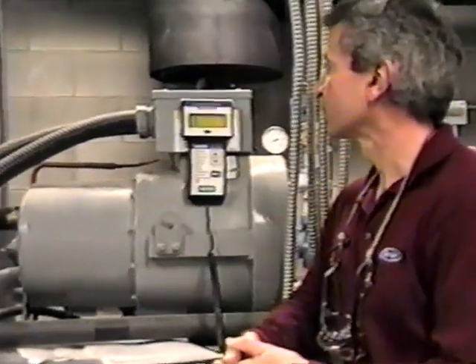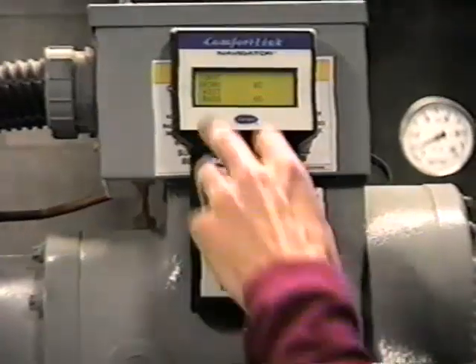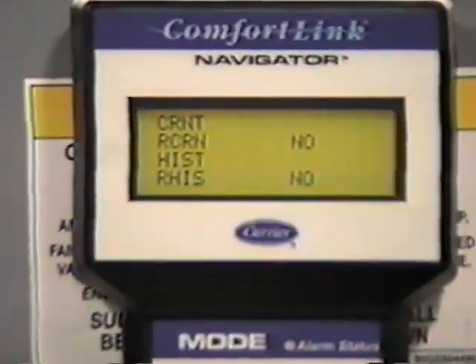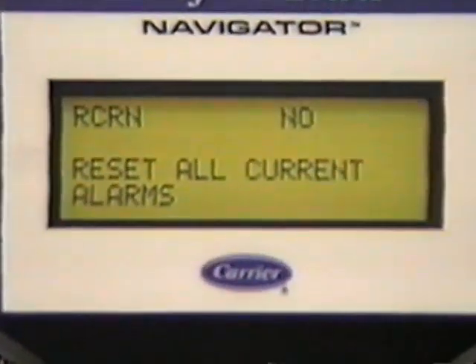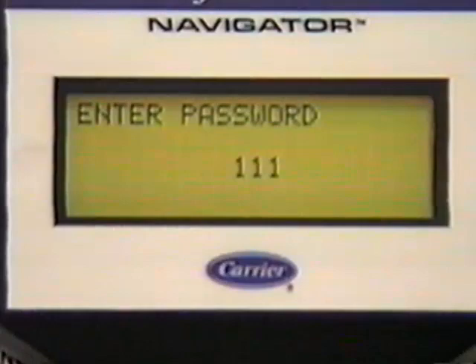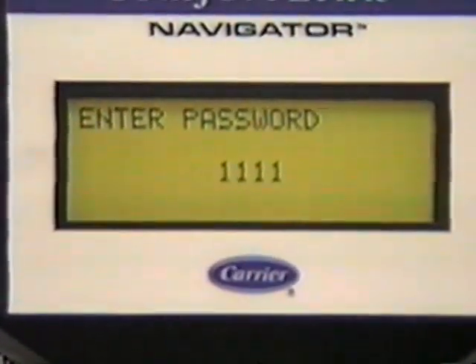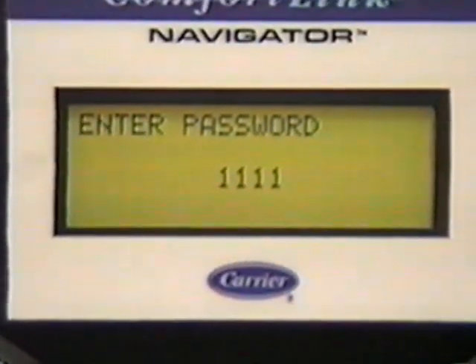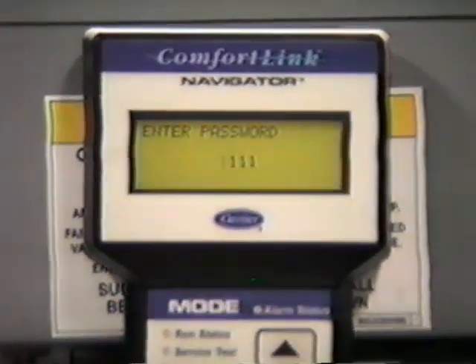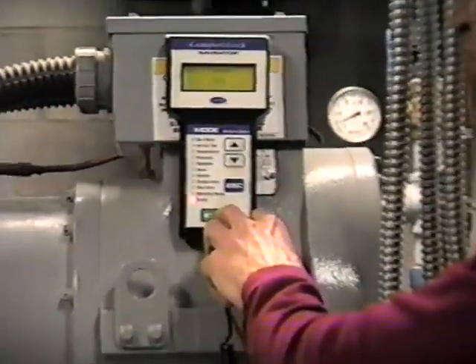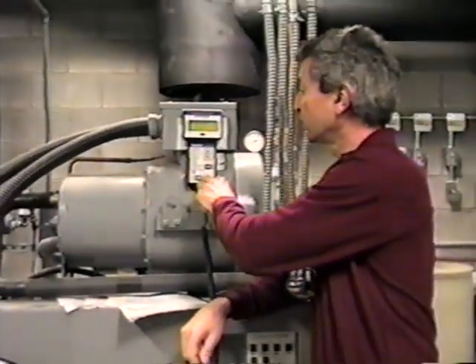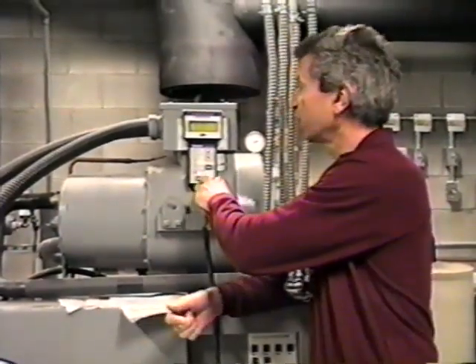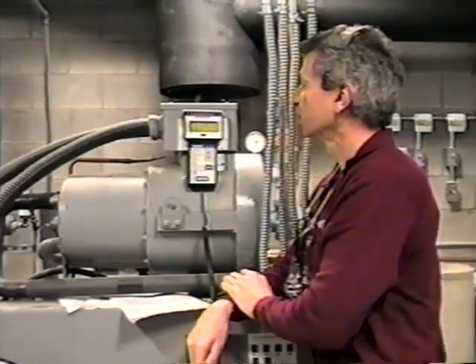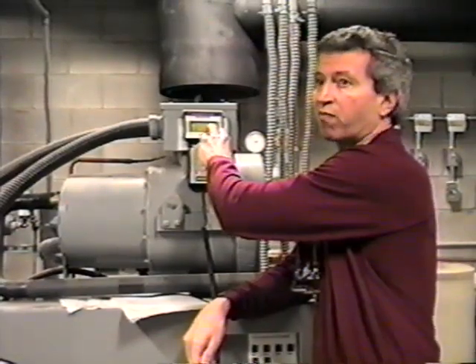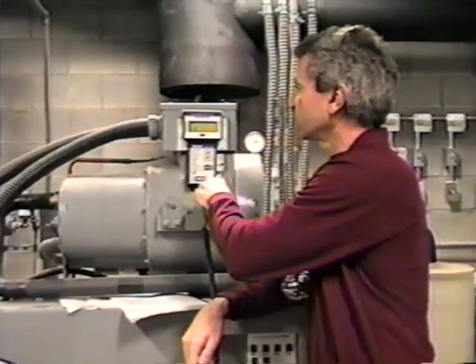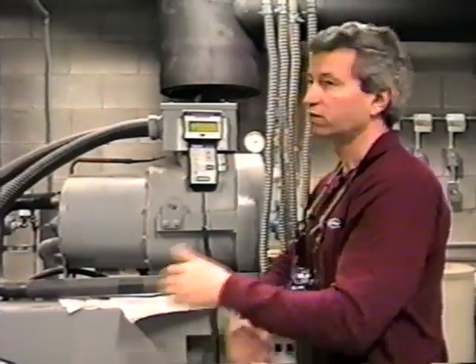You can clear it by going into this RCRN. And if you expand on that, it says reset all current alarms. So if you hit enter, it's going to ask you for a password, because we don't want anybody just coming by here and resetting alarms. The password is defaulted to 4 ones. It's going to be displayed here, so when it says 1, you can either change that number or hit enter, and then it'll go on to the next digit. Hit enter again, and enter again. Then it's going to say reset current alarm. Now you'll see the no blinking. You can change that to yes and hit enter, and essentially it's reset.